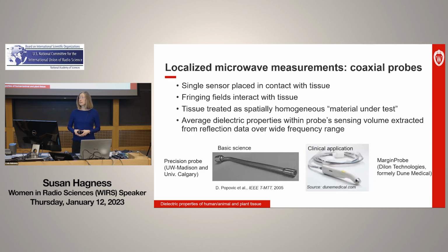These dielectric properties of biological tissue are measured oftentimes using localized measurements with coaxial probes. And so in this case, an open-ended coaxial probe is placed in contact with the tissue. The fringing fields at the end of that open-ended coax interact with the tissue. The tissue can be treated as the material under test, assumed to be homogeneous within the sensing volume of the probe. And then the average dielectric properties within that sensing volume are extracted by measuring the reflection coefficient at the aperture and then converting that to the unknown dielectric properties. And these properties can be measured with laboratory probes, like a precision probe that we developed many years ago with the University of Calgary. There are clinical applications that use dielectric probes for characterizing tissue for clinical purposes.